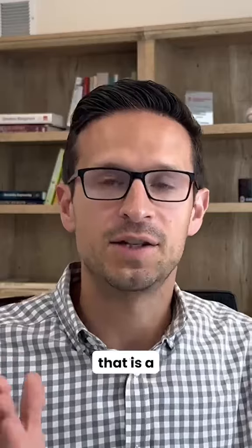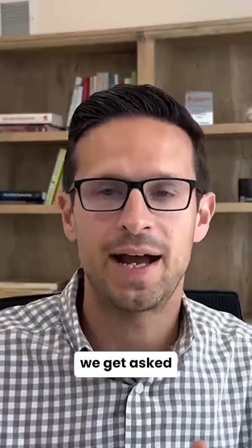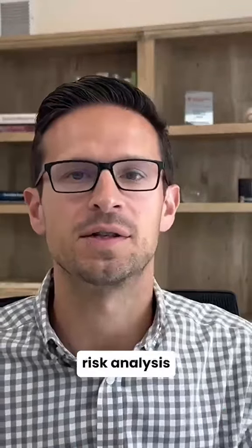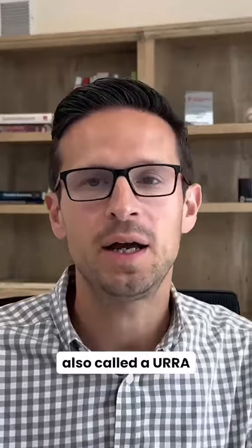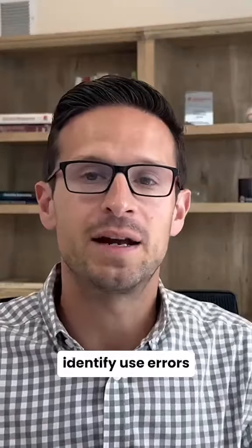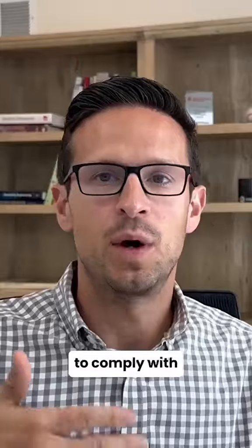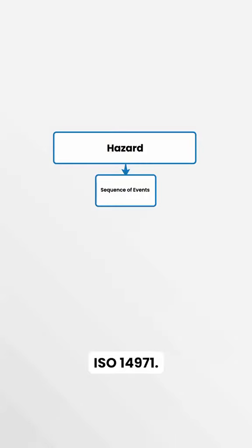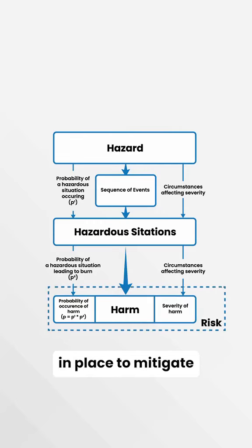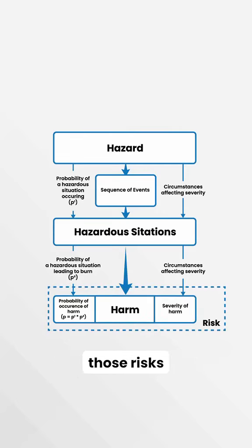Yeah, that is a great question. This is a question we get asked a lot: why do we have to create a use-related risk analysis, also called a URRA? And there's two major reasons. The first reason is to identify use errors to comply with ISO 14971, right? One of the requirements of ISO 14971 is to identify use errors and make sure we have controls in place to mitigate those risks appropriately.